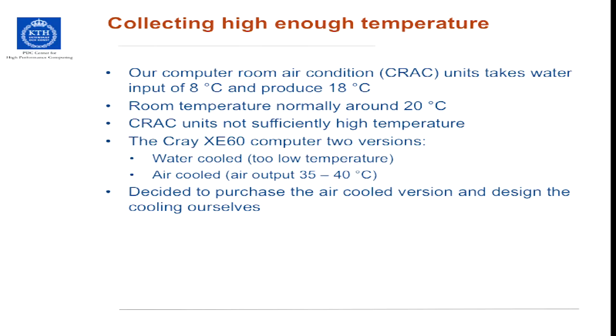But the entire thing is to be able to collect high enough temperature to be able to reuse the energy. So in this case, you need at least something which is above 20 degrees. The incoming air to a building needs to be at least, normally, like 20 degrees in the room, right? So we need something which is a little bit more than that to be able to transport it away and heat the incoming air into the building. So we need 25, 30 degrees from the computer itself to be able to reuse it for this purpose.